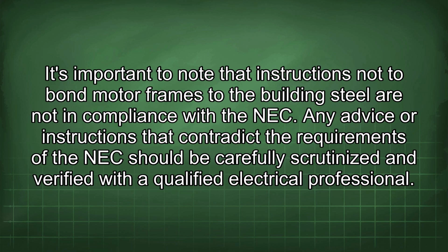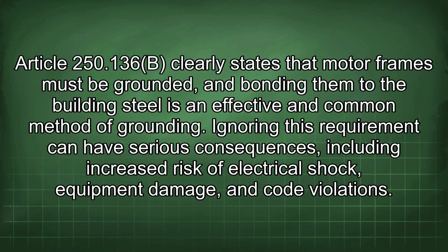It is important to note that instructions not to bond motor frames to the building steel are not in compliance with the NEC. Any advice or instructions that contradict the requirements of the NEC should be carefully scrutinized and verified with a qualified electrical professional. Article 250.136(B) clearly states that motor frames must be grounded, and bonding them to the building steel is an effective and common method of grounding. Ignoring this requirement can have serious consequences, including increased risk of electrical shock, equipment damage, and code violations.